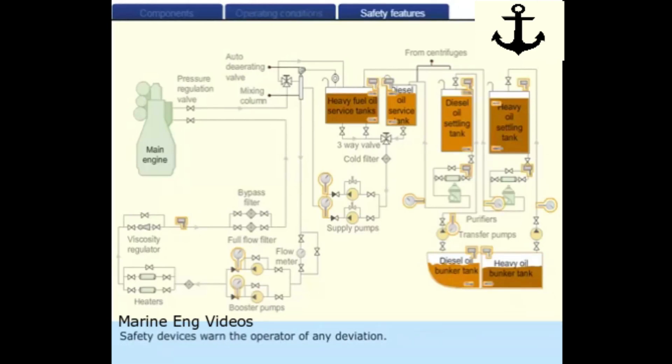Safety devices warn the operator of any deviation. The highlighted devices of the system act as frontline safety provisions which trigger the actual safety alarms, shutdowns, or isolations. Temperature transmitters, pressure transmitters, level transmitters also provide first level of protection against system breakdowns.